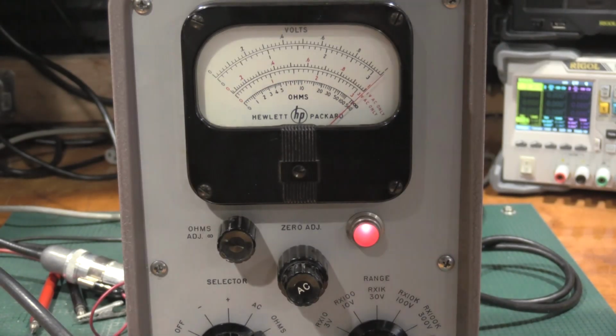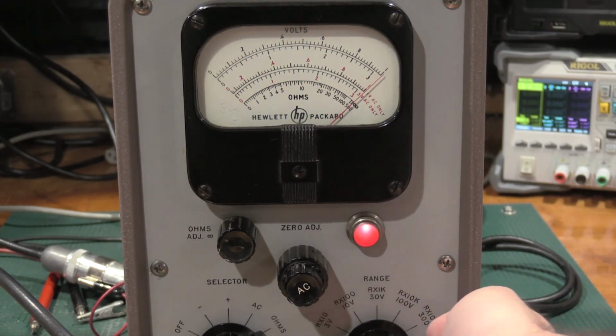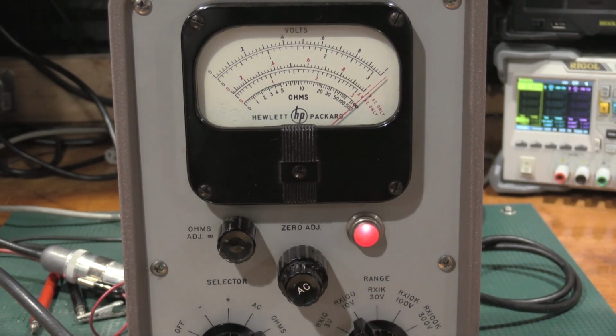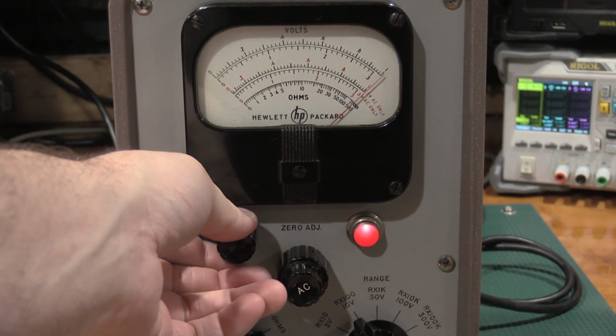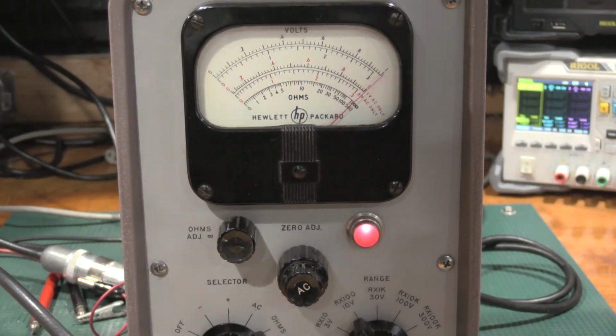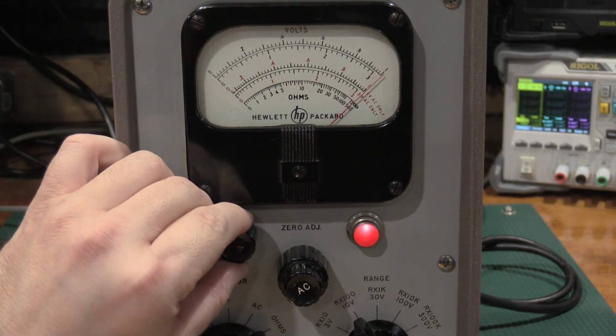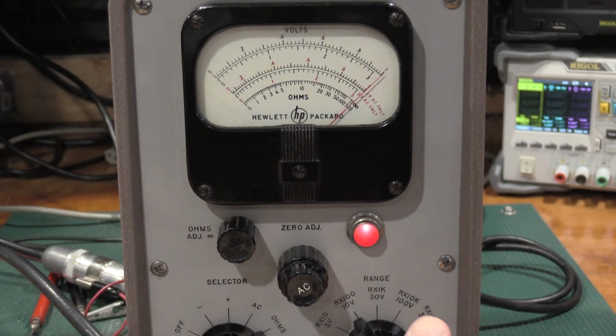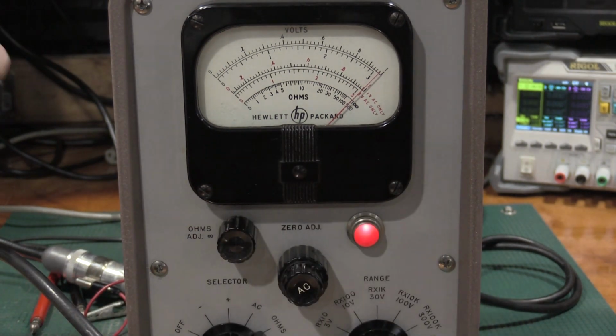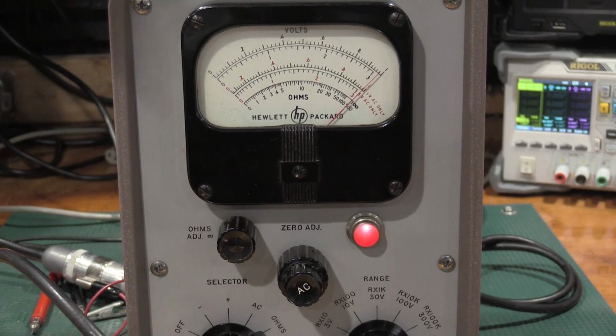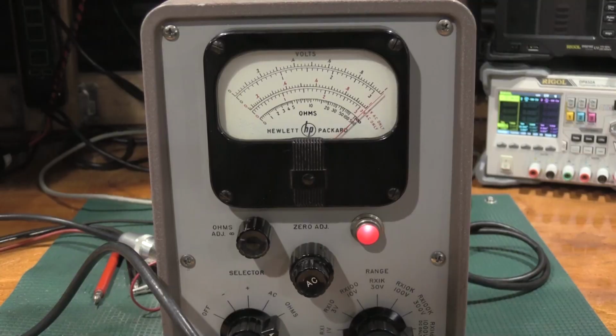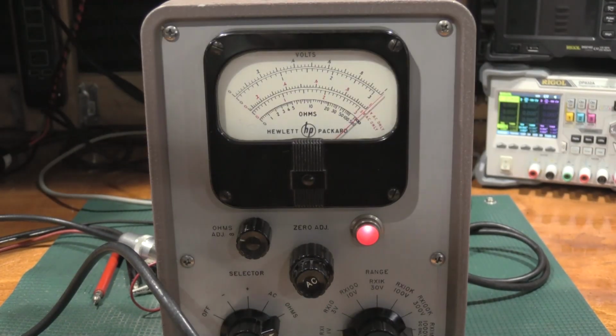Okay, so for the ohms position, we need to zero set on the 10 volt range. And it's probably going to need adjustment. So set for infinity. Go back to the 1 volt range. If it's off, set the potentiometer on the back of the unit. Do this a couple times, and the ohms range is adjusted. So time for me to do that. And there we are, zeroed on the 1 volt range.